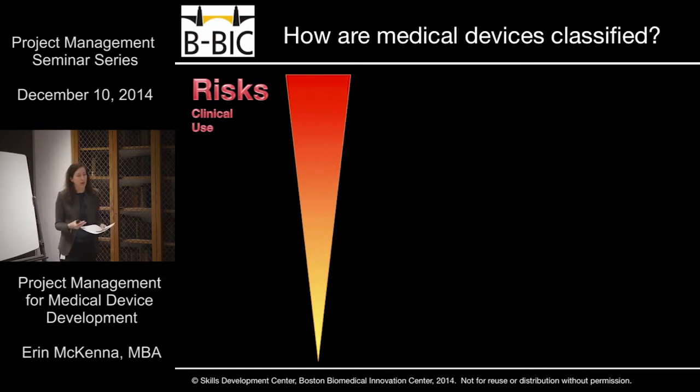So heart failure, anything really involving the heart, especially if you're putting something mechanical in there, is probably a class 3. Use is also an important factor to consider. If the actual intervention itself presents high risks to the patient, to the physicians, requires a higher level of training and scrutiny, those will also drive things up into the class 3 level.